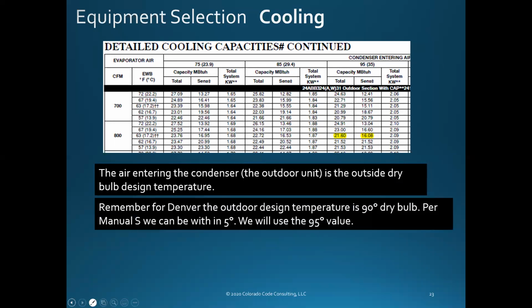Denver is 90, and our design was 90, so you can be within 5 degrees either way. We could either use the 85 or the 95, or interpolate between the two if we wish - software actually has a way to do that within it. I don't mind, let's go to the higher one, because the capacity is going to be a little bit less, isn't it?